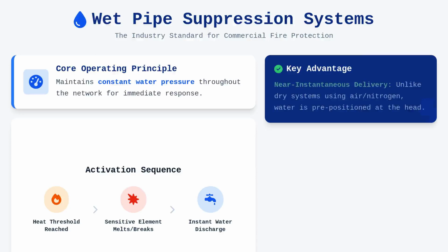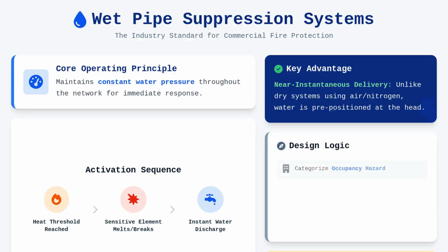Unlike dry systems that rely on pressurized air or nitrogen, the wet pipe system provides near instantaneous water delivery, which is why it is preferred wherever freezing conditions are not a concern. From a design perspective, we must categorize the occupancy based on its fire hazard potential, which then determines the required water density and the design area for our hydraulic calculations.